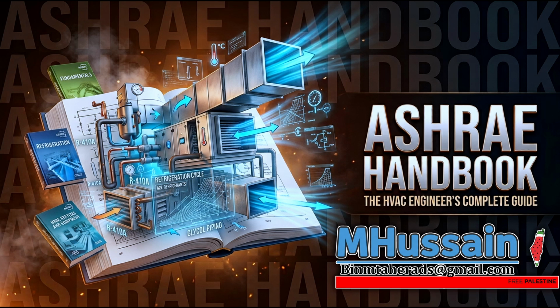Yeah, that's a good way to put it. And nowhere is that more evident than in Chapter 20, which covers data centers. Let's talk about that because the AI boom has completely upended server technology. It has rewritten the rules. Our sources note that this chapter was heavily updated to align with modern IT demands, specifically the inclusion of direct-to-chip and immersion liquid cooling. It seems like the era of just blowing cold air down an aisle of servers is totally over. It basically has to be over because the physics of the new processors demand it.